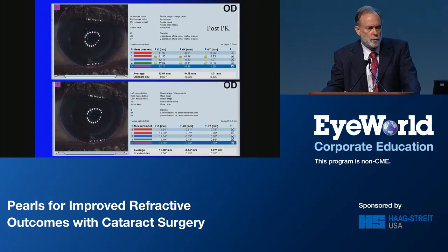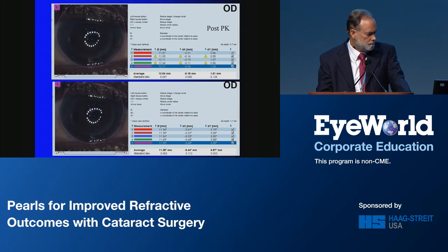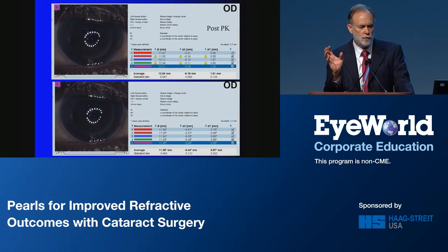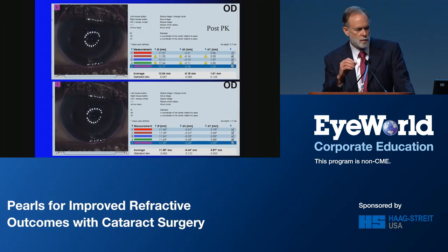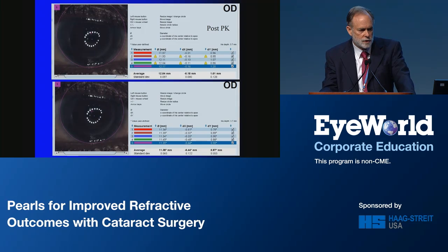If you look at the purple line that outlines the limbus on the left side, you can see that it's offset a little bit, and it's out over onto the sclera or the limbus a little bit more than it should. So what my technician did was they made the circle for the limbus smaller, and they moved it a little bit over the center to the left and downward. If you look at the 2 pictures, the upper one is before they repositioned it, and then they repositioned it down below. With a lot of abnormal eyes that make the readings difficult, this has been helpful for us to make our calculations a little bit more accurate.